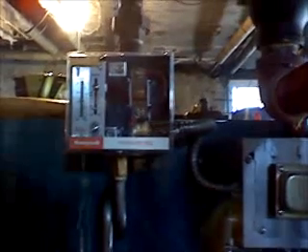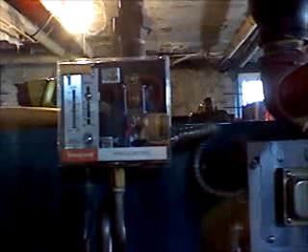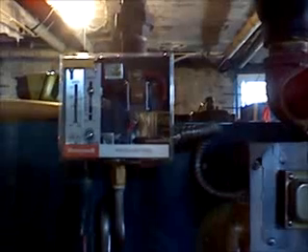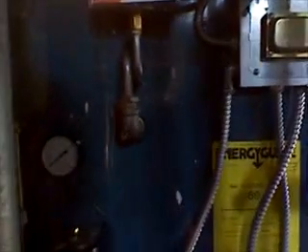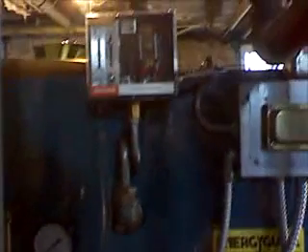Here's our pressure control safety, which the thermostat is usually satisfied before the pressure control actually kicks in. I have this set extremely low at about 1/2 pound, because again, you don't want pressure on small steam systems and single residential homes.